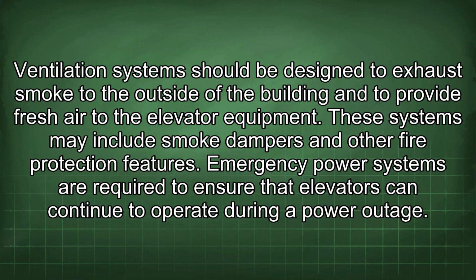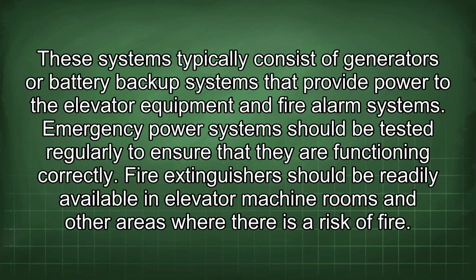These systems may include smoke dampers and other fire protection features. Emergency power systems are required to ensure that elevators can continue to operate during a power outage. These systems typically consist of generators or battery backup systems that provide power to the elevator equipment and fire alarm systems. Emergency power systems should be tested regularly to ensure that they are functioning correctly.